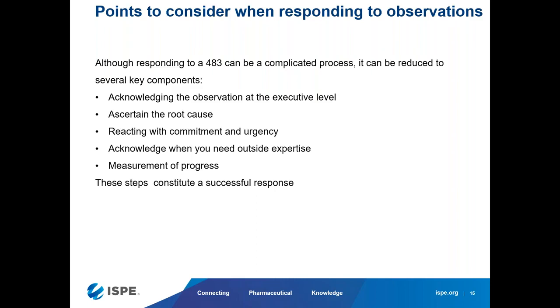But there was no root cause, and they kept repeating 'operator training, operator training' until my engineer said, no, this is a facility design issue. Every time you open the door, the air actually moves over to the person. Plus, a lot of the surface monitoring plates weren't doing well either.